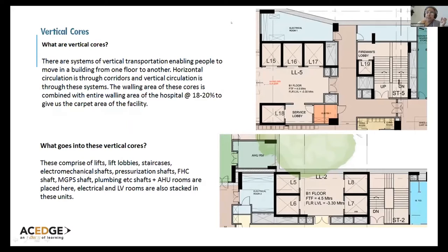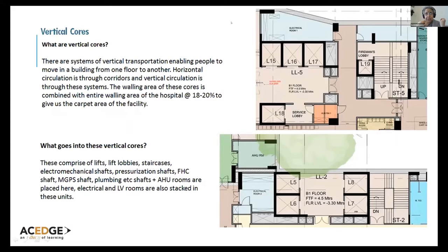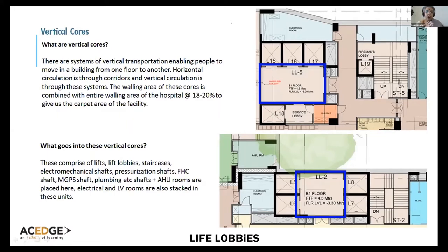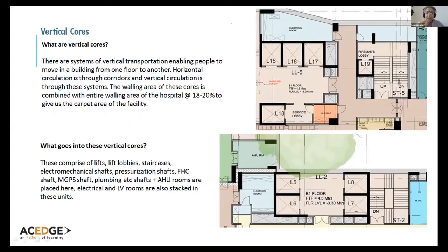What goes into these vertical cores? There are lifts, staircases, and lift lobbies. In India, we often try to put lifts along corridors, thinking people will come out and go to their spaces, but that's not a good practice. Lift lobbies must be enclosed — enclosed because of fire laws, otherwise you can leave them open for aesthetic reasons. A lift lobby has to be pressurized because it's a fire core.